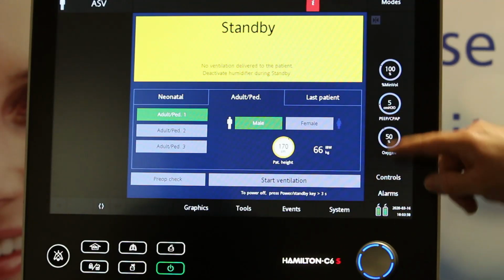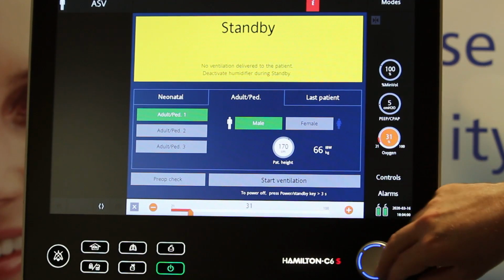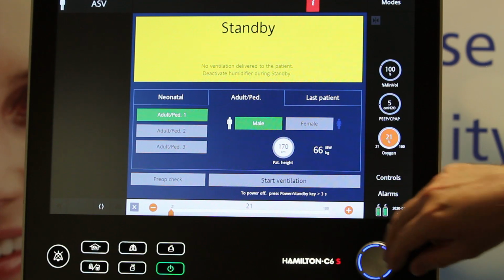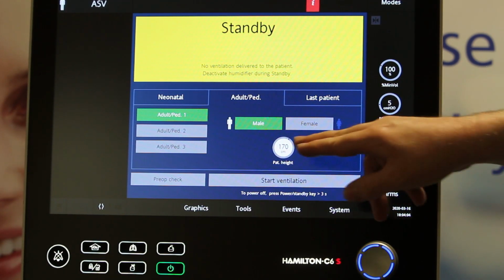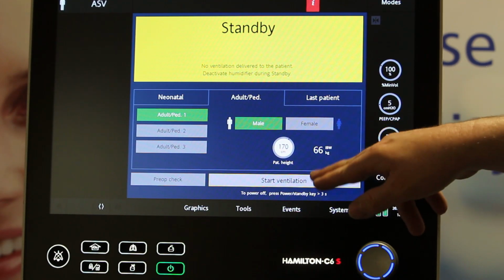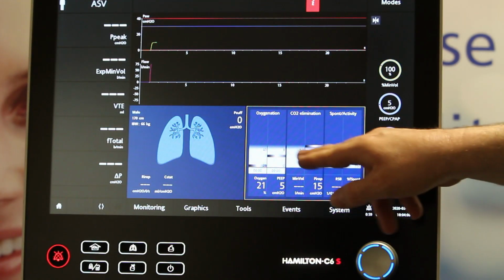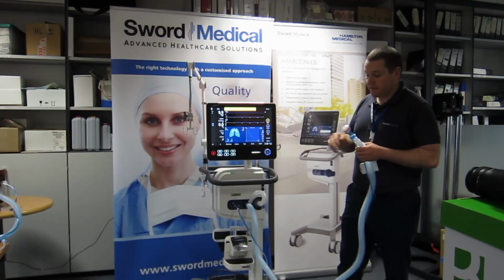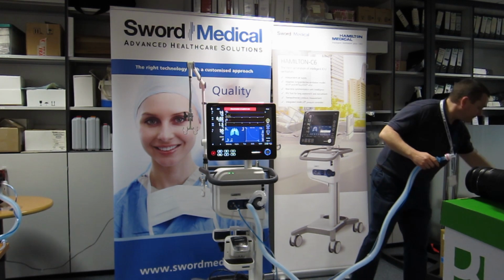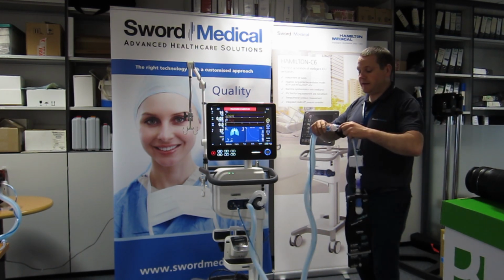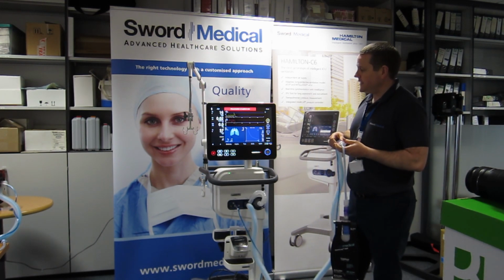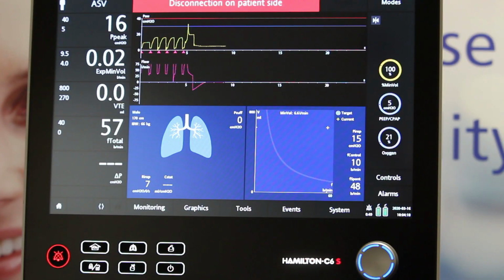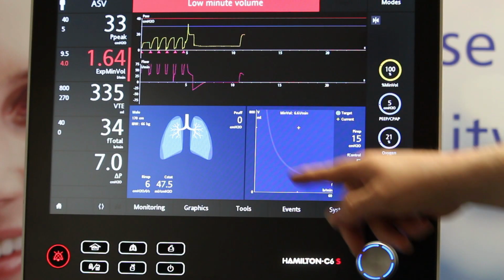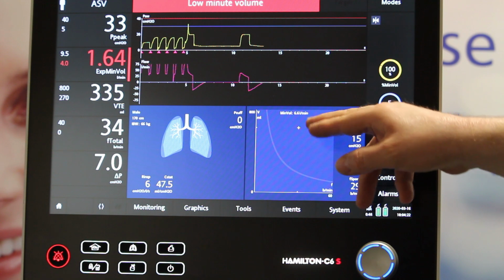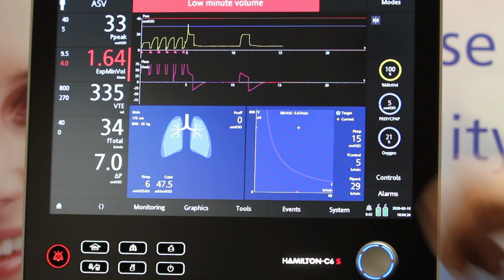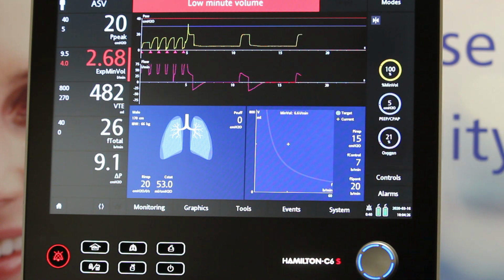So I put in my height. I'm going to dial down my FiO2 to 21% because we're running on room air. So put in my height and then start. So what the ventilator is doing now, when I put my lung on, the ventilator is going to give 3 test breaths into the lung that I've just put on. And if we look at my ASV graph here, we can see the target minute volume is 6.6 litres per minute.